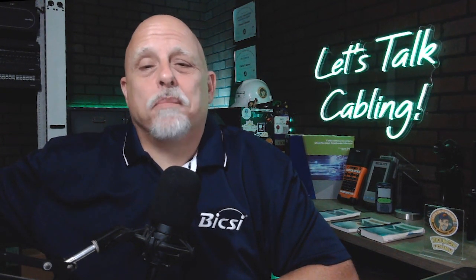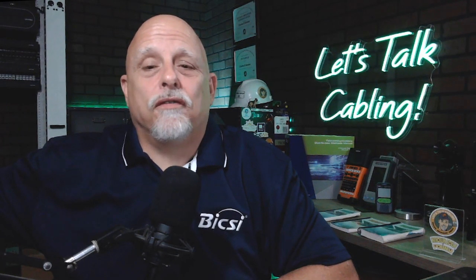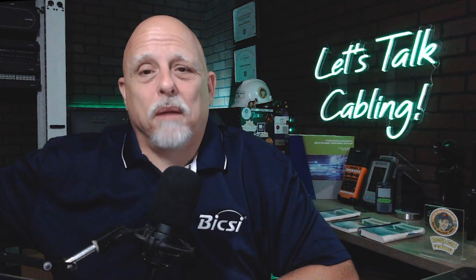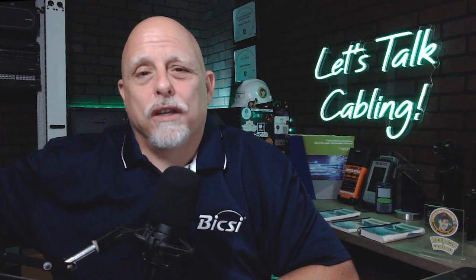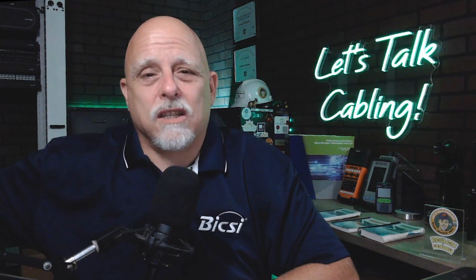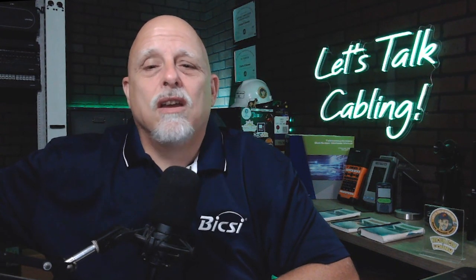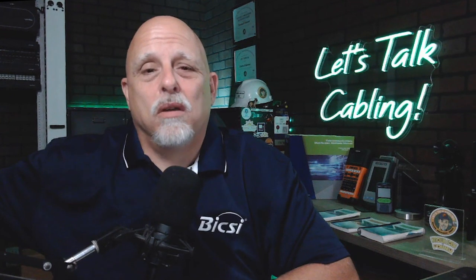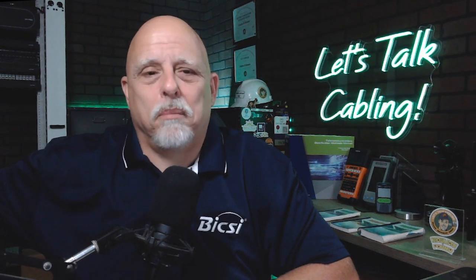An issue often experienced by installers when installing field terminated plugs is, as I mentioned, those field terminated plugs can be rather large. The most common complaint I hear, this being a problem, is on wireless access points, especially those that have closely spaced ports. You see, there's just simply not enough room for those two large field terminated plugs to sit side by side.